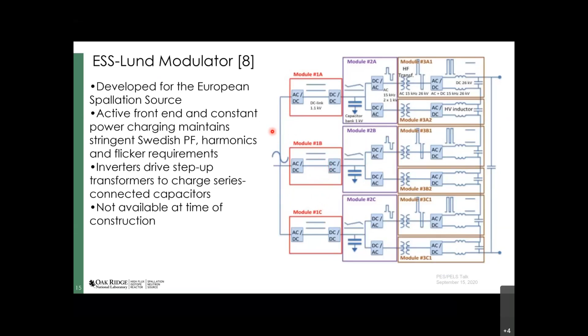So this modulator, in spite of the fact it runs at 660 kilowatts of average power, has a very, very near unity power factor and very little harmonic and flicker production. So it's quite attractive from a utility perspective. And then we come to the SNS modulator, which we call the high voltage converter modulator.